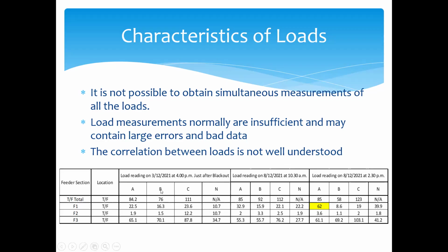These values were obtained in 2021 when I was working as an energy management engineer. We have a meter installed in every transformer. We can get the total load of the transformer. All the currents in the LV feeders are measured, and it is given in this first row, transformer total, but it doesn't measure neutral current. So the A phase, B phase and C phase currents are given in this row for one particular day.